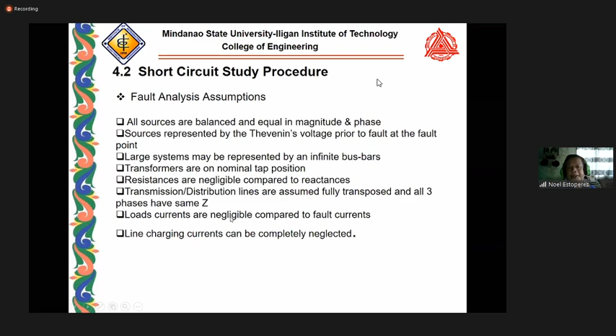Distribution or transmission lines are assumed fully transposed, and all phases have the same impedance. Load currents are negligible compared to fault currents, so sometimes we will be neglecting the load. Except in instances, especially in industries, where the presence of induction motors as loads means we cannot neglect that one.